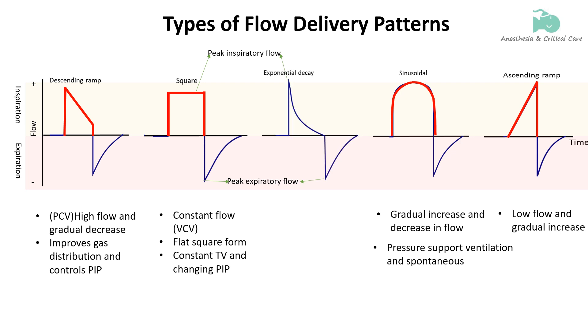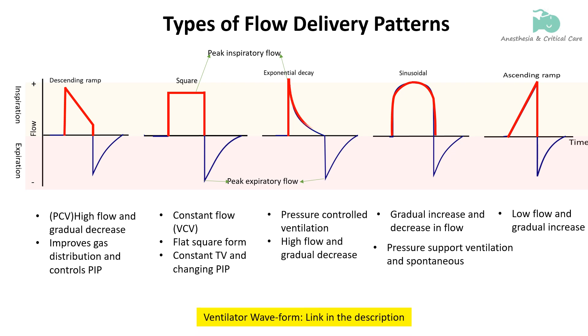The exponential decay flow pattern, seen in pressure-controlled ventilation, starts with a high flow rate that gradually decreases as the lungs fill. This pattern helps distribute air more evenly and reduces peak airway pressures, making it gentler on the lungs. Unlike the descending ramp where flow declines linearly, in exponential decay the flow decline is gradual, giving it a curved appearance.